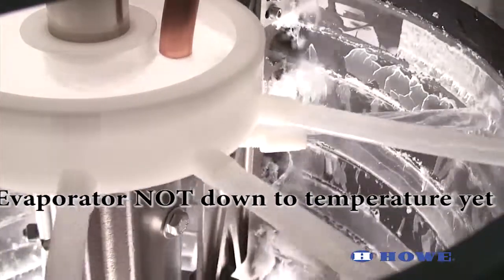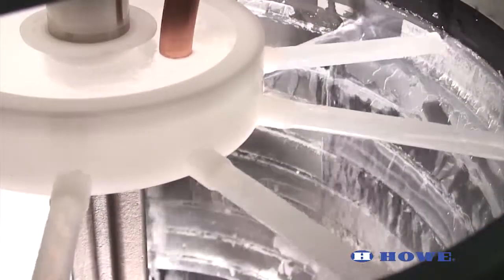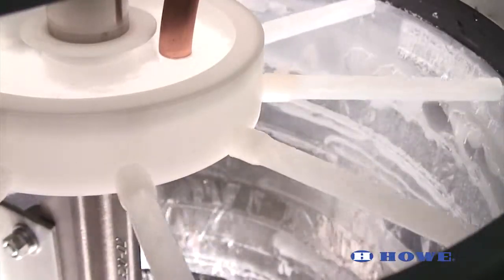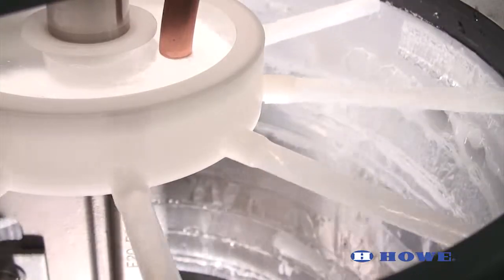Before adjusting the TXV, check to ensure the evaporator is operating at the correct pressure. Adjust the EPR valve as necessary to achieve the correct evaporator temperature.